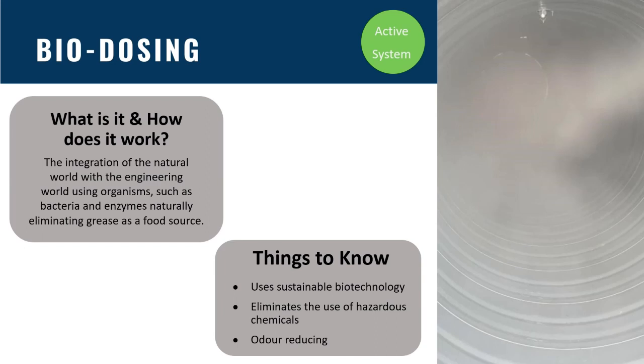The first one on our agenda is biodosing. What is that and how does it work? Well, biotechnology is the integration of the natural world with the engineering world using organisms such as good bacteria and enzymes. So bacterial solutions are used in high or low pressure systems with spray injection nozzles that distribute the solution throughout the ventilation system by spray, mist or fog. The solution then adheres to the ductwork, and the good bacteria produces enzymes that break up and digest the food source, which in this case is fats, oils and grease. And the food source itself causes the good bacteria to replicate and convert to biofilm until reactivated again.